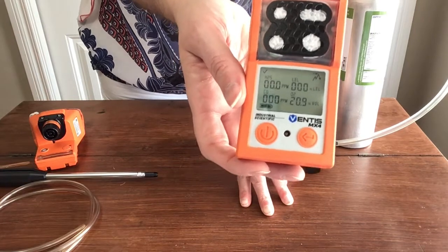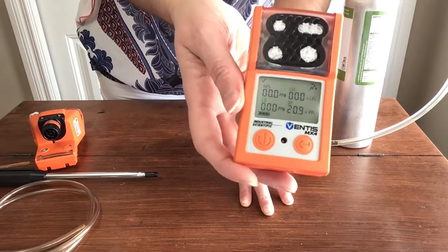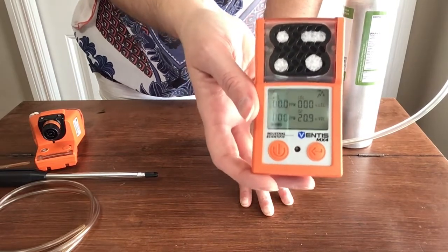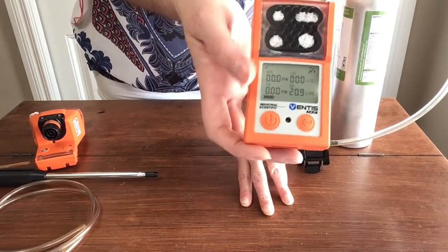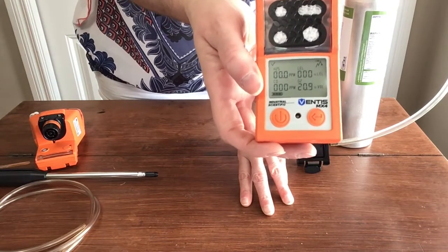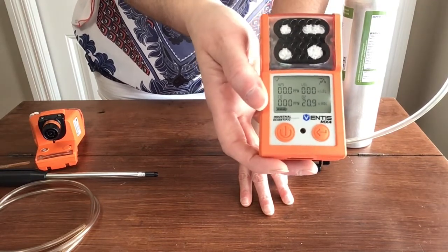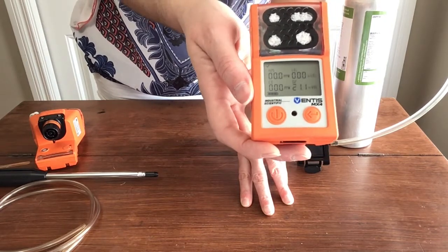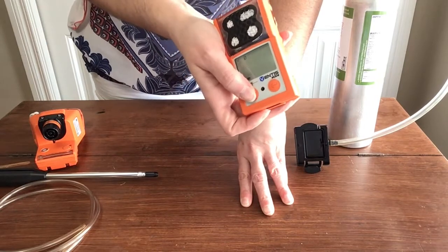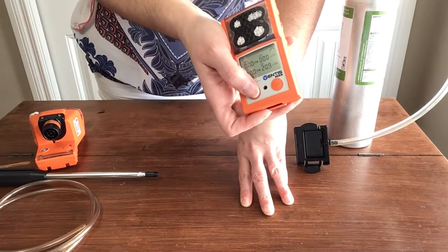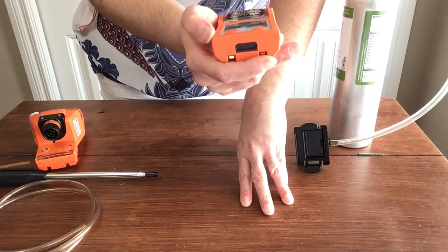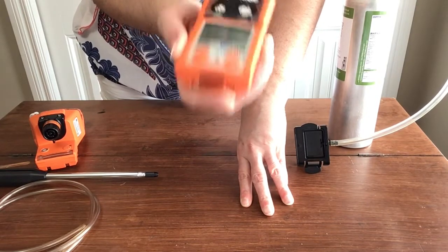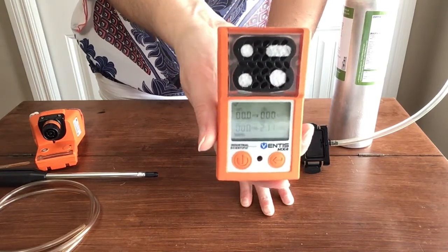The reason that you want them to clear the peaks before they go into the workplace is because if this does alarm for any reason while they're in there, let's say they're in a confined space, and it starts to alarm, you'll want them to be able to actually check on this screen to determine what the issue was and why it started alarming. And if you haven't cleared your peaks, then obviously you won't be able to gather that information. Okay? So then before your worker heads into the workplace, we're simply going to have this on the main screen.